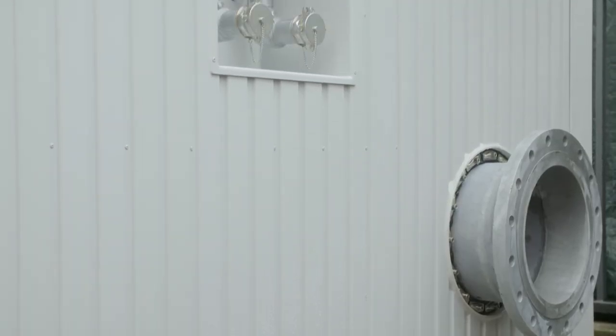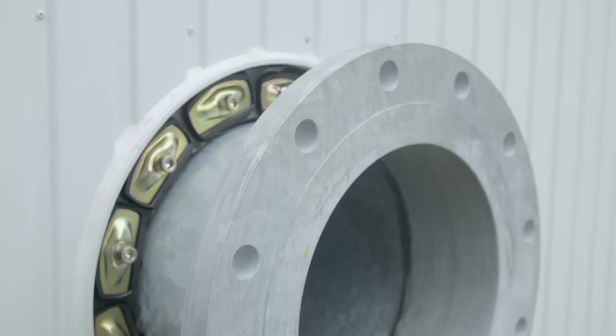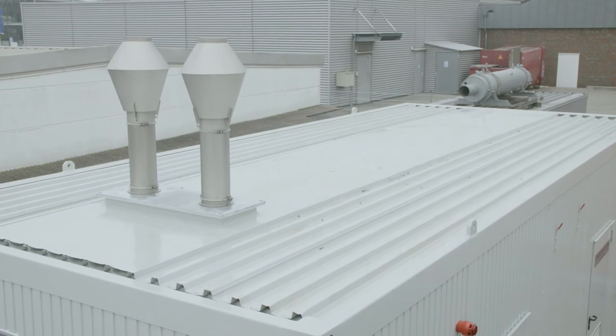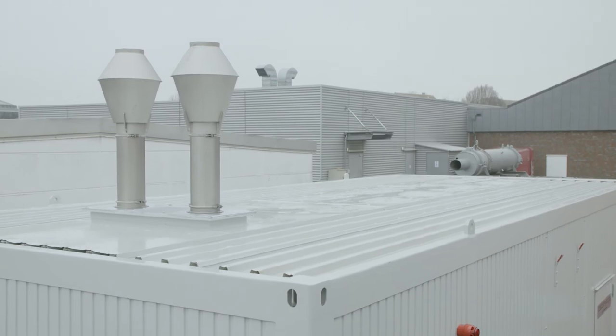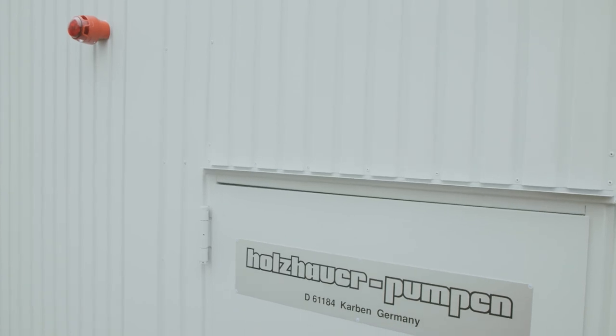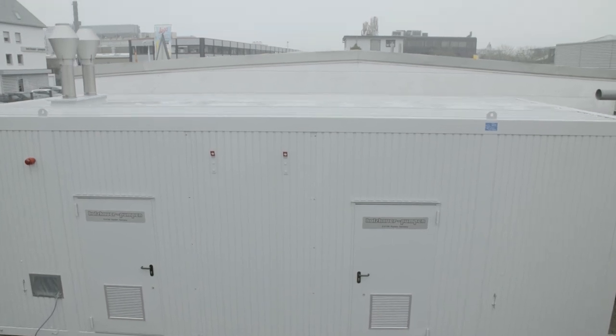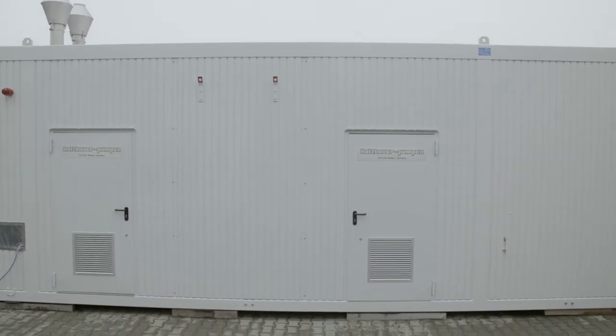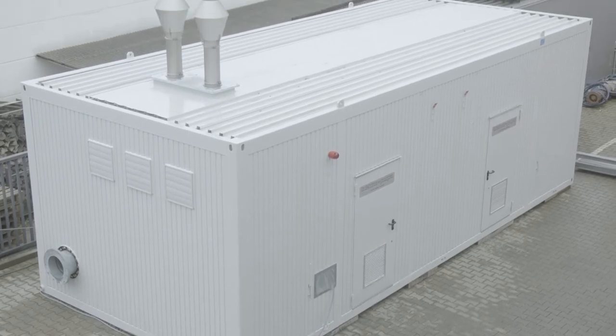With clear interfaces for easy and fast connection at your site, ANSI flanges according to customer specifications are provided for the interconnecting pipes outside the pump station. So much performance in such a compact and clearly structured form — the turnkey Simplex Fire Pump Station Series Firekont Simplex WRHD, designed according to NFPA and FM guidelines. With a length of 9.2 meters, a width of 4.1 meters, a height of 3.15 meters, and an operating weight of 22.5 tons, with maximum water capacity.